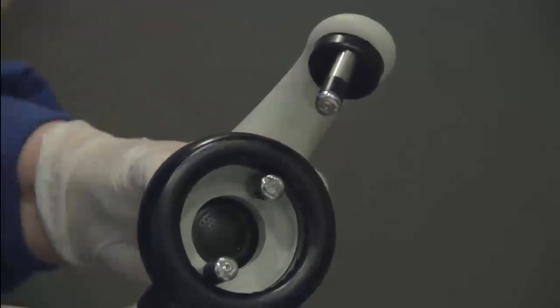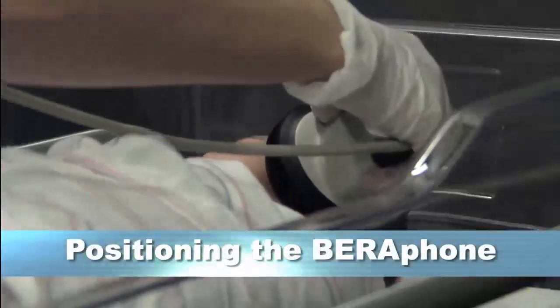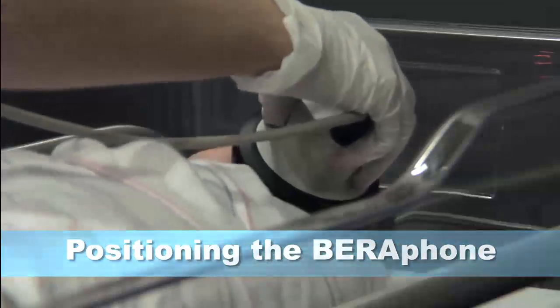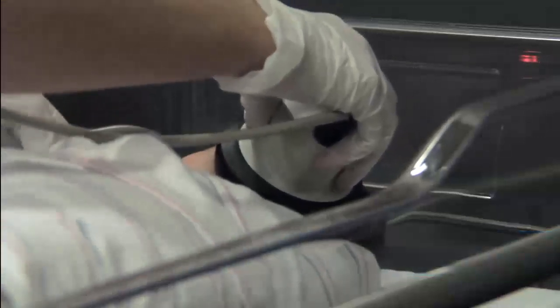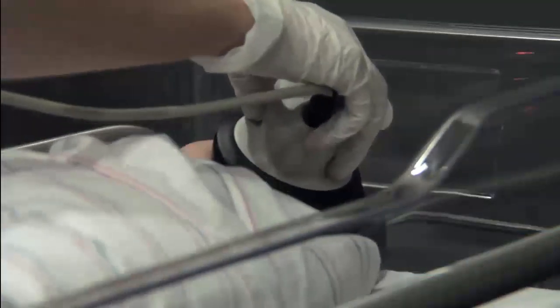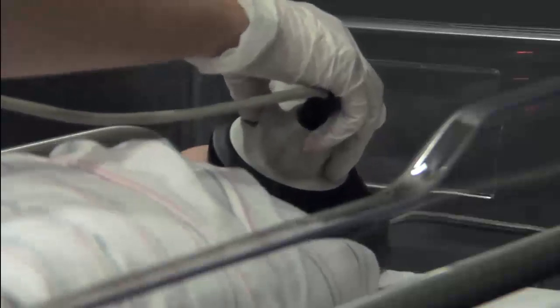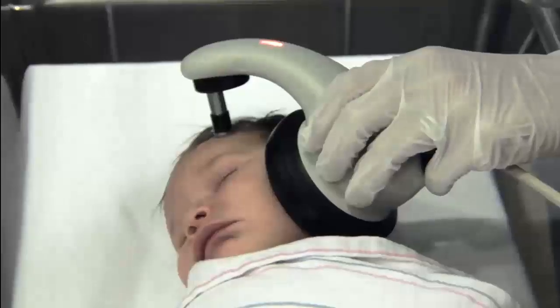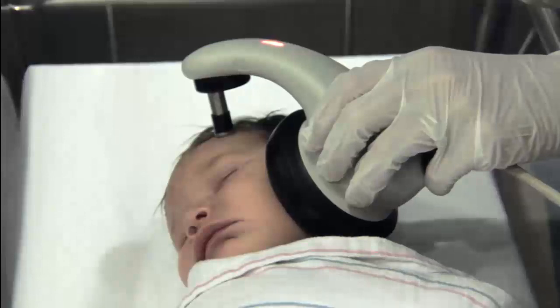Place the mastoid electrode on the prepared skin. Lay the top of the BERAphone down gently so that the ground electrode and vertex electrode make contact with the prepared skin sites. Verify that the ear cushion is making contact with the baby's skin all around the ear with no large gaps between the cushion and the skin.